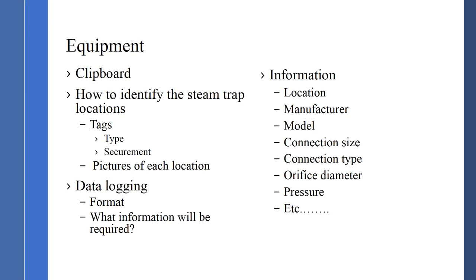Required information fields include location, manufacturer, model number, connection size, connection type, internal orifice diameter, operating pressure, downstream pressure, the type of condensate return system the steam trap discharges into, and how to evaluate inlet pressure for the steam trap if it's on a modulating system. The SOP goes into depth telling team members how to gather each piece of information accurately.